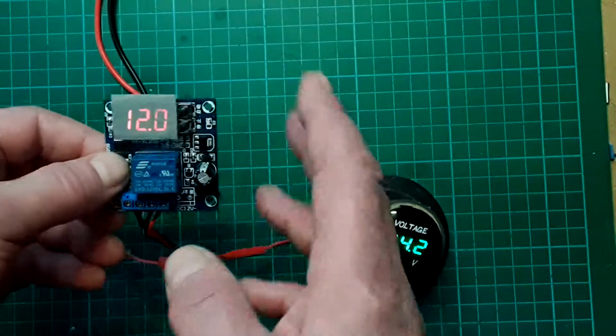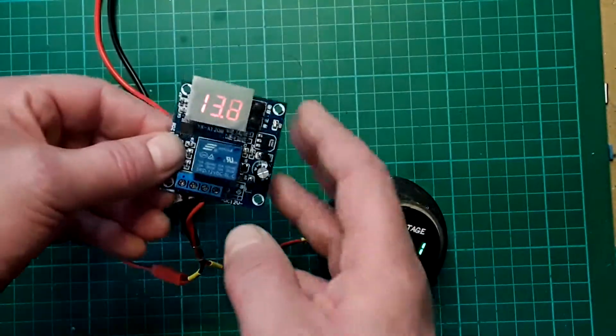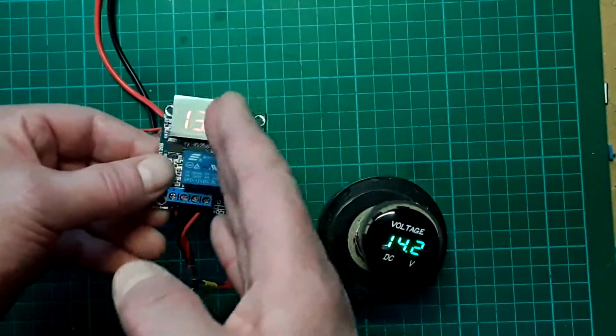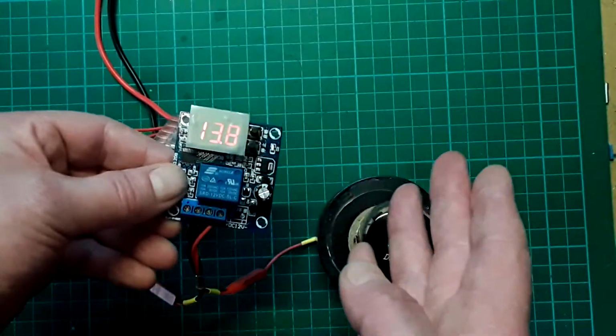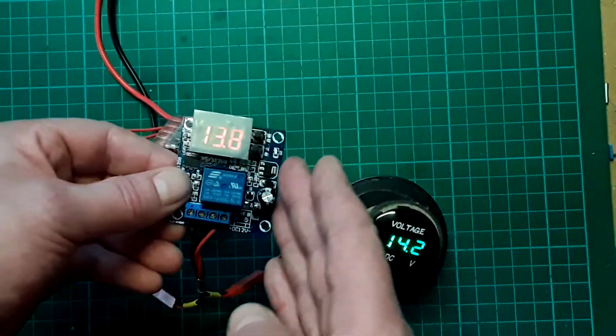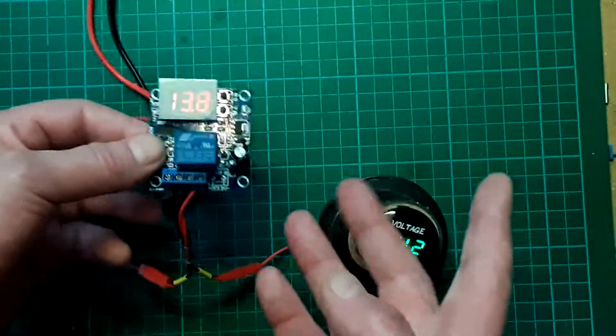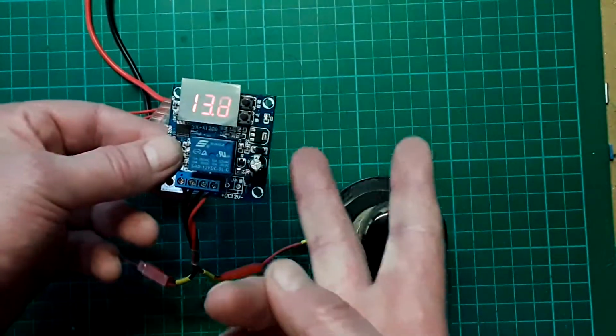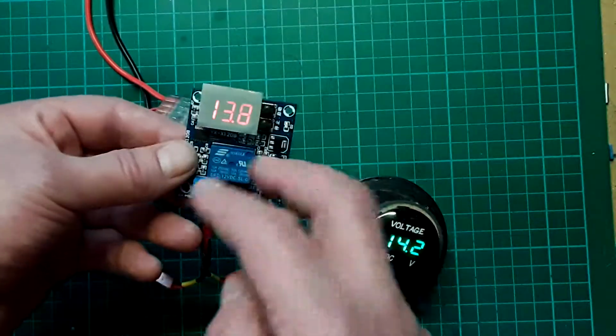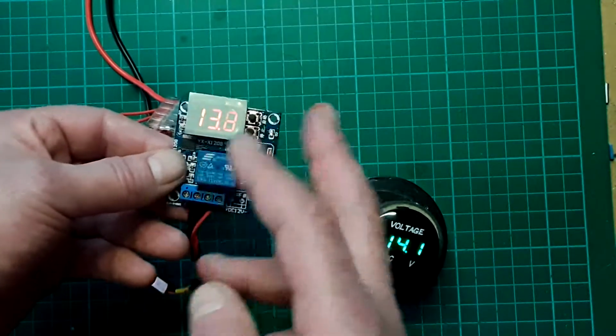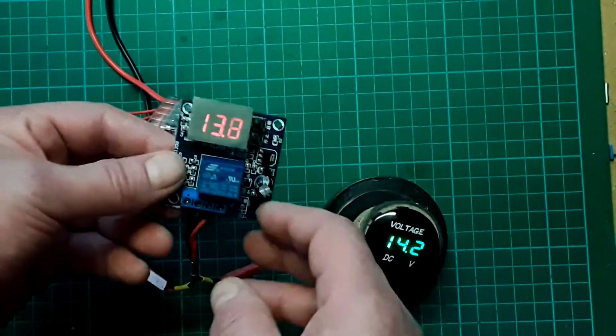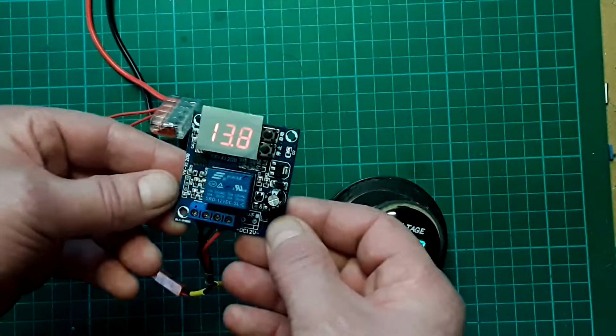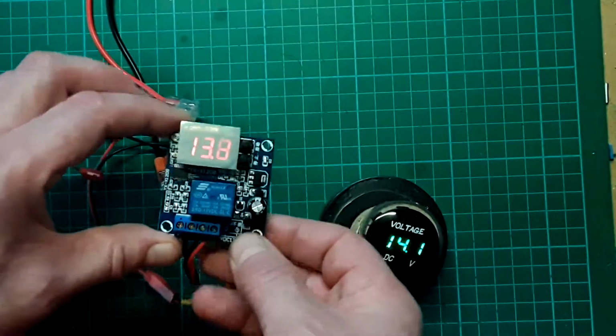Now the reason for having hysteresis in this is because if you've got a battery with a load on it and it starts discharging, it'll disconnect, and the terminal voltage on the battery will start rising - it'll drift upwards. So this would just be shuttling, toggling up and down throughout the various bandwidths. So you can set that - that's quite nice to be able to do.